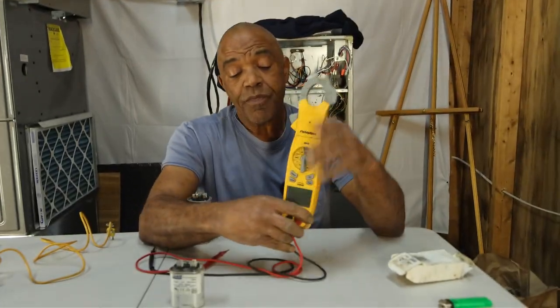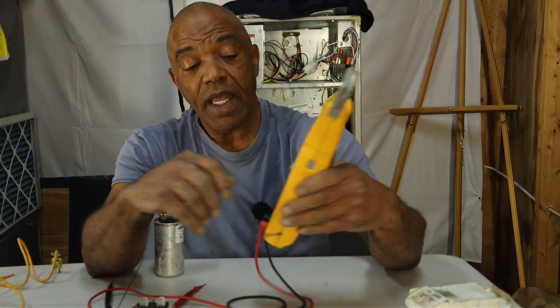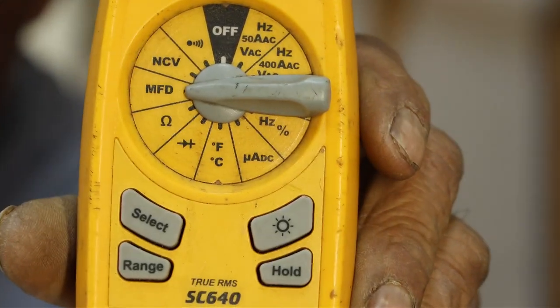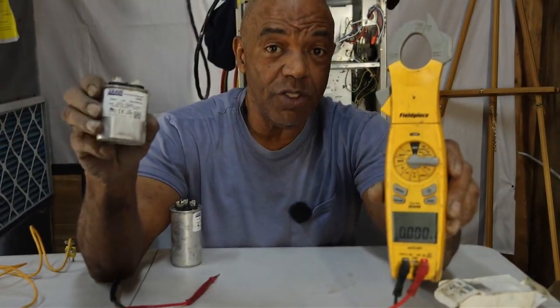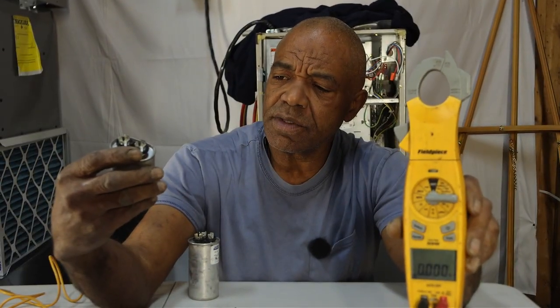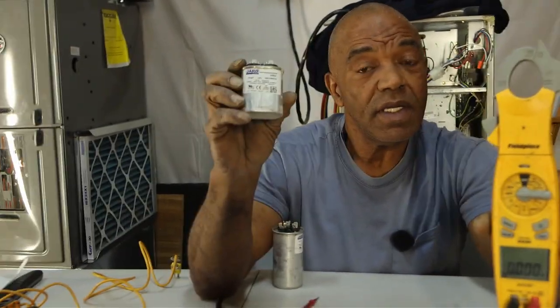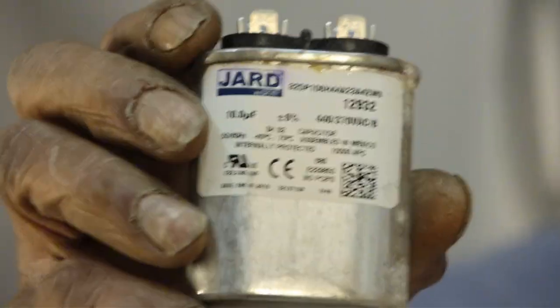That's why, because this is basically a start capacitor. It helps the motor get started. So one of the things we can do with our amp probe is we can dial up where it says MFD. That's where I have my arrow pointed at right now. Now, this for an indoor fan motor is a 10 UF capacitor. They often will be, you have 3 UF, 5 UF, 10, 15, 12.5, you have a 7, you have a 7.5. It's a multitude of different capacitors.